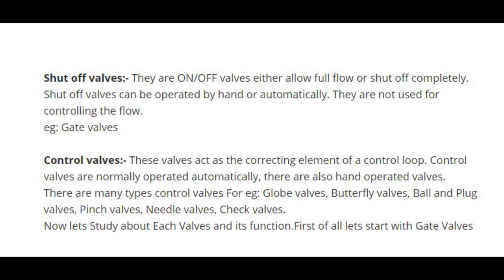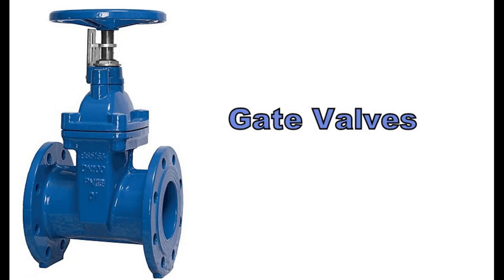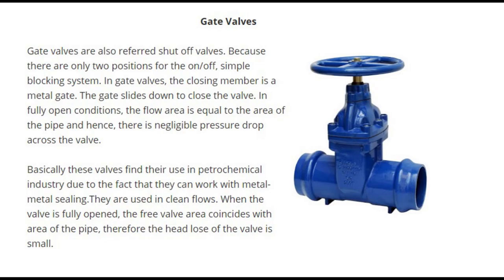Gate valves are also referred to as shut-off valves because there are only two positions: on and off — a simple blocking system. In gate valves, the closing member is a metal gate that slides down to close the valve. In fully open conditions, the flow area is equal to the area of the pipe, and hence there is negligible pressure drop across the valve.